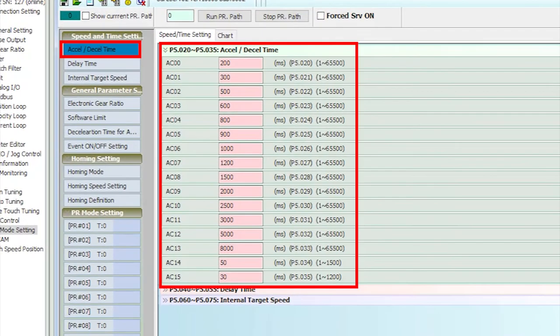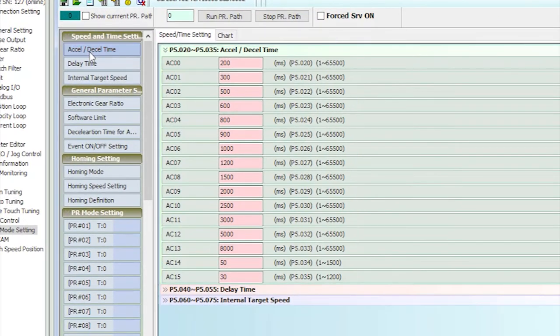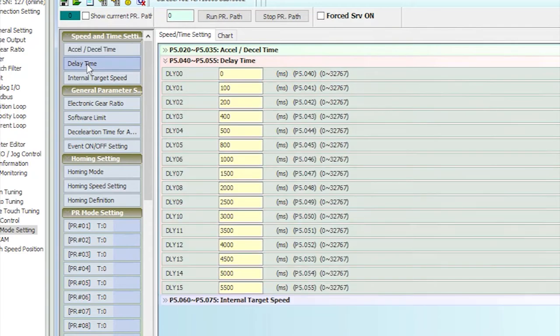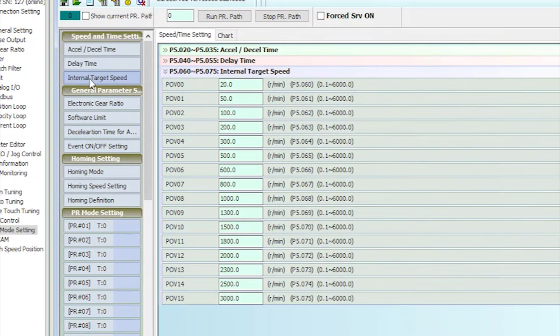Now we just go down to the motion section and select the PR mode. Here are the 15 ramp times that we can use for either acceleration or deceleration, the 15 delay times and the 15 target speeds. These defaults are fine for this demo, but you'll want to enter whatever numbers you need for your system.